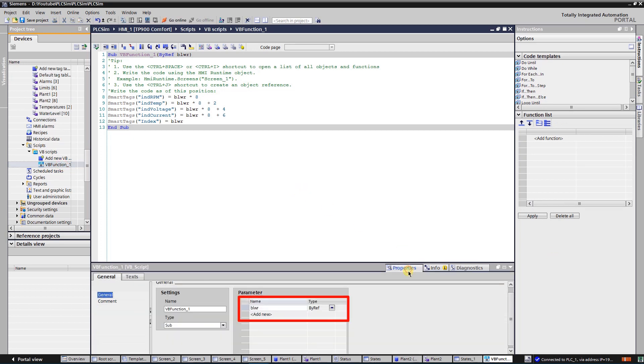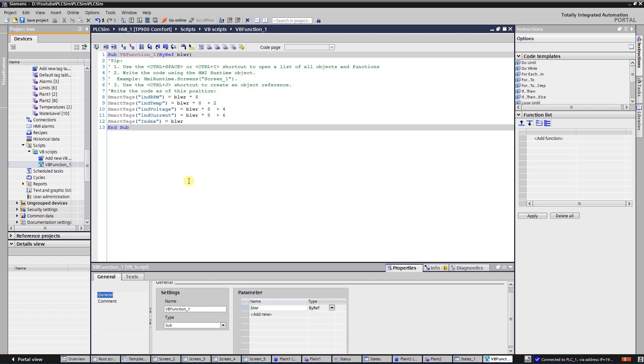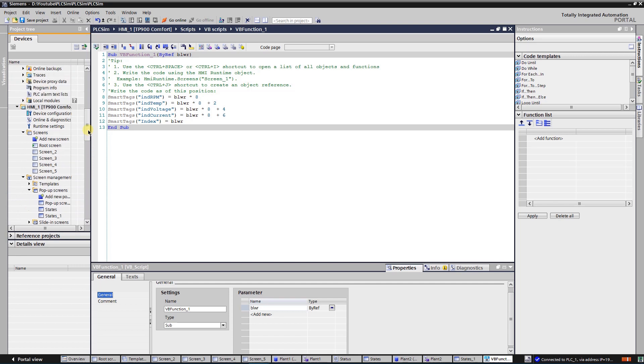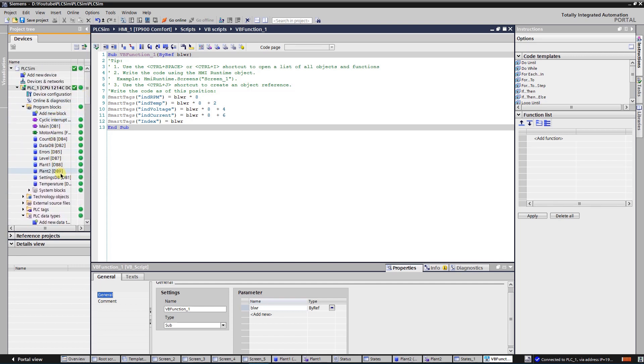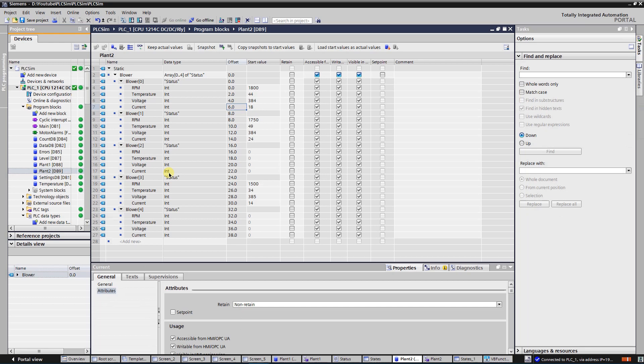Create a new VBScript with one input parameter for the blower number. Multiply the blower number by 8 to get the value of the RPM of the corresponding blower. The length of each array element is 8 bytes — your value will be according to the length of your array element in bytes. So for the first element with index 0, RPM will be 0 multiplied by 8 equals 0. For the next element it will be 1 multiplied by 8 equals 8, and so on.